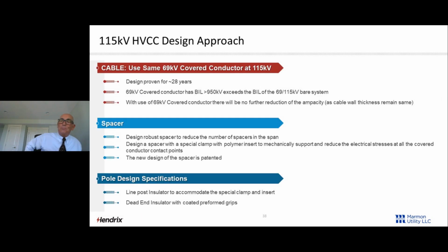So, the design approach. As you're probably going to guess, it's the same exact design approach we have for 5, 15, 25, 35, 46, and 69. We're using the same 69 kV covered conductor for 115. Why? There are a lot of reasons. We don't want to use more material. It's getting heavy. We have more than sufficient 60 hertz withstand and BIL. The charging current on the jacket is acceptable. We don't want to increase the weight and increase the cost.